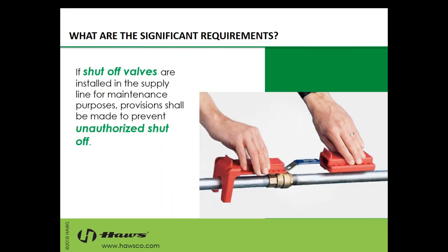Now, shutoff valves are another important part of the standard in that if there is a shutoff valve installed in the supply line for maintenance purposes, provisions need to be made so that we prevent unauthorized shutoff. This usually means a lockout device for the shutoff valve, making sure that an employee doesn't inadvertently shut it off for some reason.